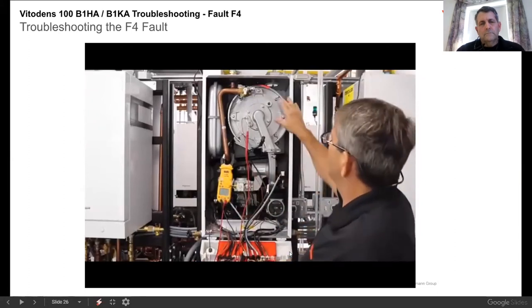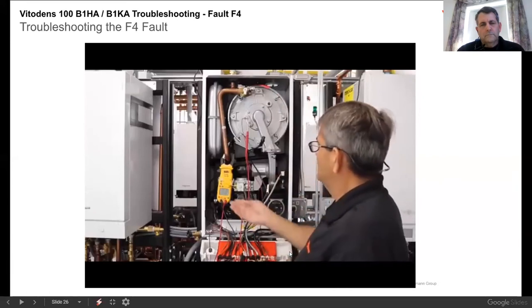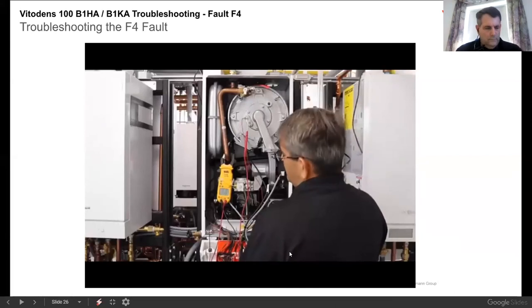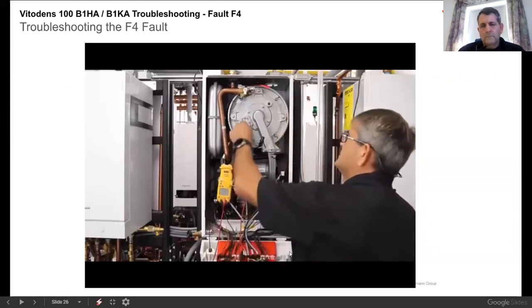So the boiler is running, so we can check that off the list. We're getting the proper flame sensor reading off there, and that's in DC microamps. As the flame gets hotter, our readings will go up higher. So now you can see that test there.